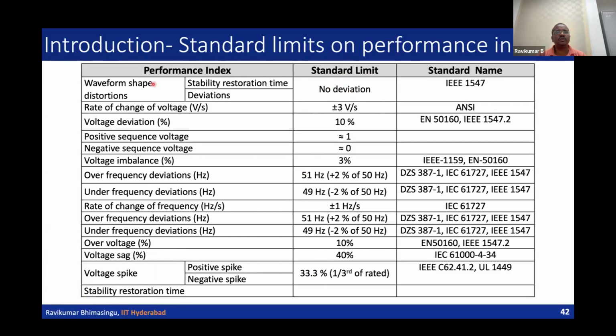Here you see voltage wave shape, meaning the distortions, how much distorted - there should not be any deviations. Rate of change of voltage should be limited to plus or minus 3 volts per second. Voltage deviations plus or minus 10%. For positive sequence voltage, it should be very close to 1, and negative sequence voltage should not be there. Voltage imbalance should be limited to 3%.